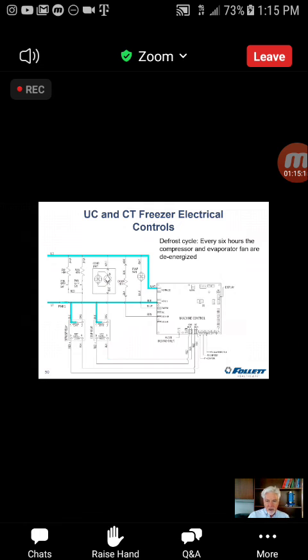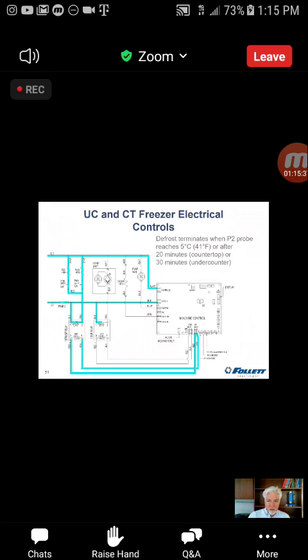And what's different here is the defrost cycle. These units defrost 4 times a day, every 6 hours. When we get to the time limit of the defrost cycle, the unit shuts off the compressor and the evaporator fan if they were running. Then we energize the coil of the defrost heater, closing the contacts and bringing on the heaters. There's a 20-minute time limit on a countertop and a 30-minute time limit on an under counter. But again, we want to terminate on temperature. It should take much less time than that.